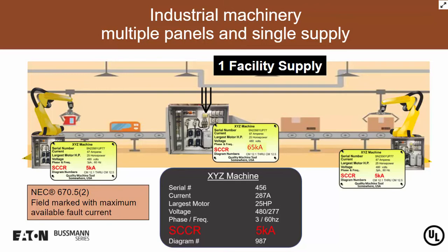It's a bit of a challenge, but you have to consider the size of the conductors going from the main panel to those sub-panels and the length of those conductors. There are programs out there that will allow you to determine what that available fault current is. You're certainly going to know the available fault current at the line terminals of the main panel. If you can somehow determine what that available fault current is at the line terminals of those sub-panels, then you can determine if they're protected. In other words, if those 5 kA ratings are adequate.